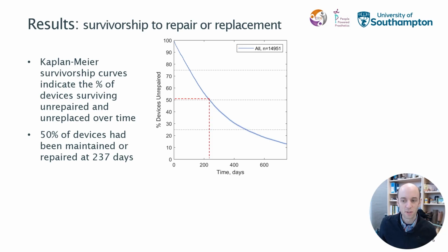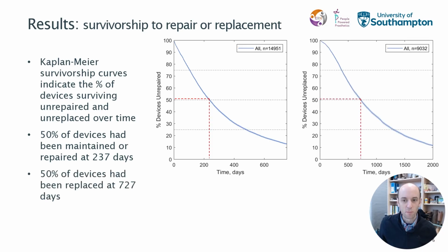We undertook the Kaplan-Meier survivorship analysis, which produces charts like this, showing the percentage of devices that survive before an endpoint, in this case repair, or in this case replacement, over time. These red lines indicate the median, the time point at which 50% of devices would be repaired or 50% would be replaced. The median for repairs was 237 days, and for replacement 727 days, approximately 2 years.